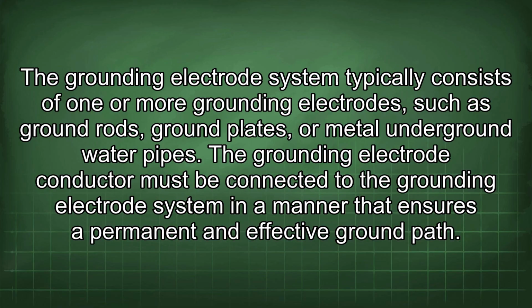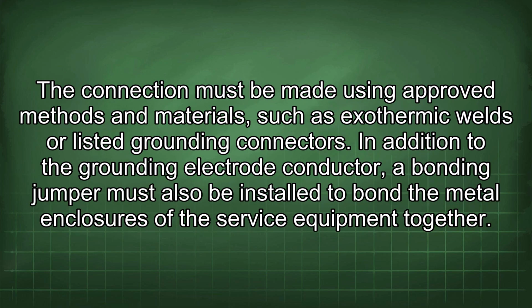The grounding electrode conductor must be connected to the grounding electrode system in a manner that ensures a permanent and effective ground path. The connection must be made using approved methods and materials such as exothermic welds or listed grounding connectors. In addition to the grounding electrode conductor, a bonding jumper must also be installed to bond the metal enclosures of the service equipment together.